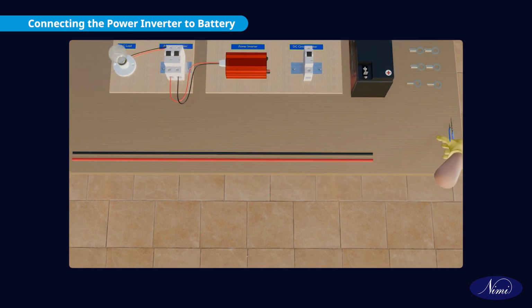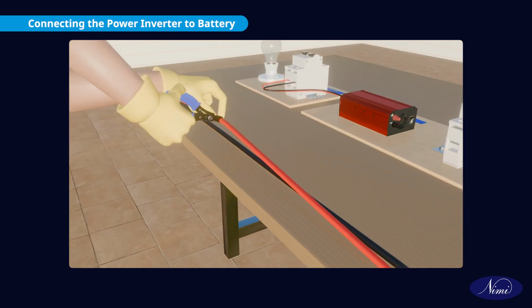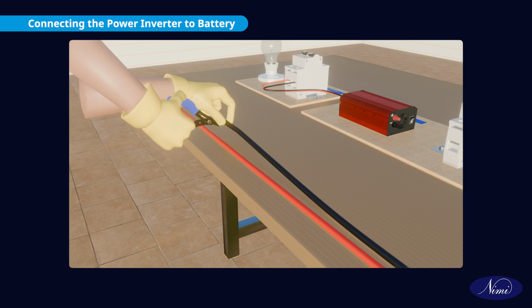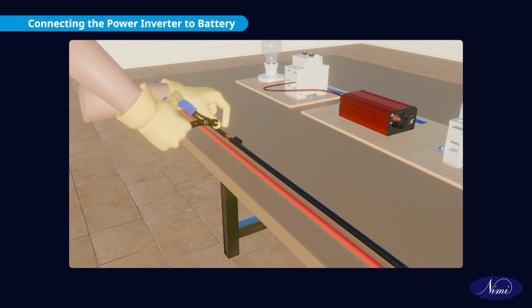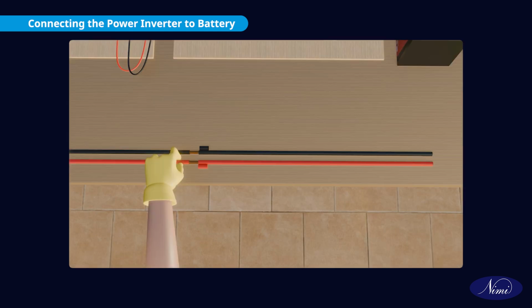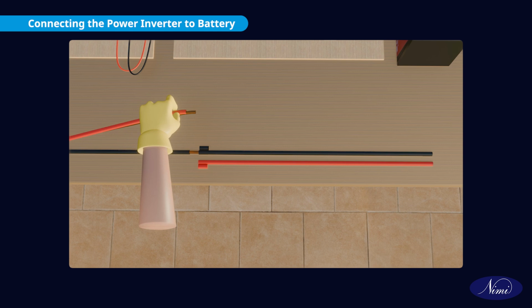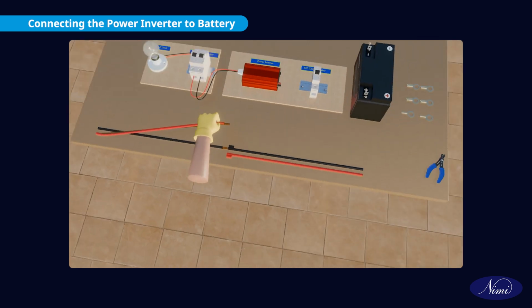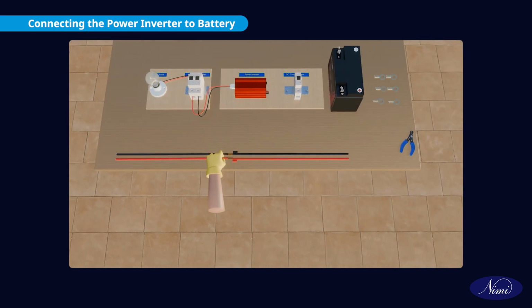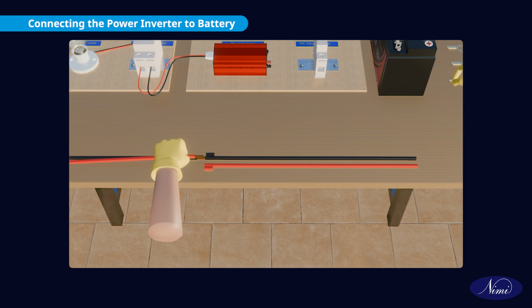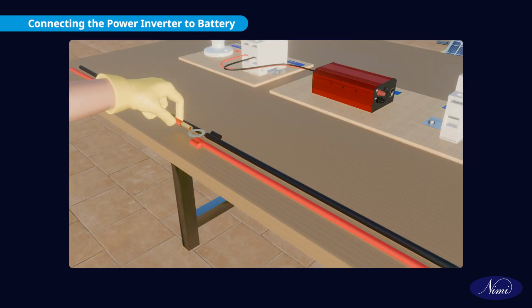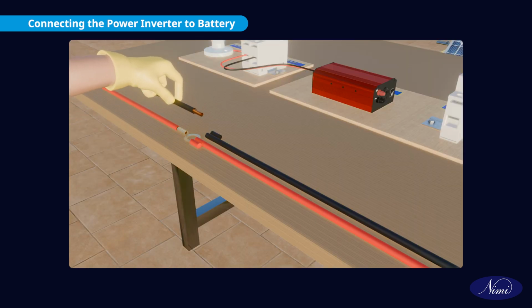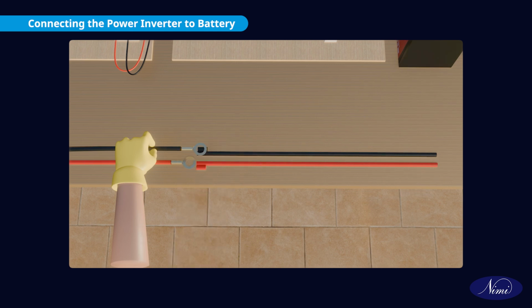Measure and cut 2 lengths of electrical wire. Remove insulation and prepare for connecting the battery to the inverter and the DC circuit breaker. Use the crimping tool with the correct slot. Crimp the lugs on one end only of both wires.